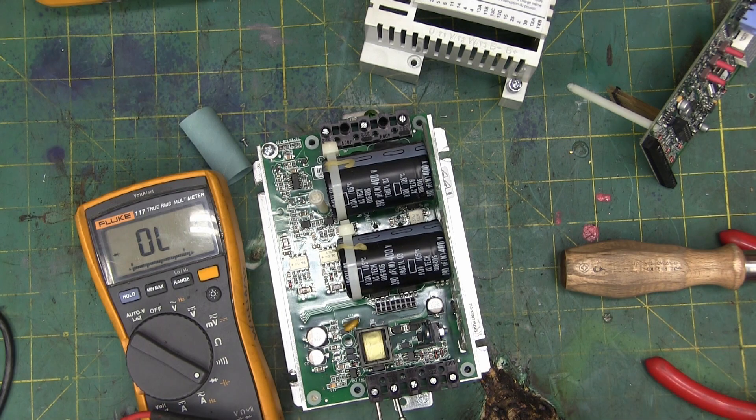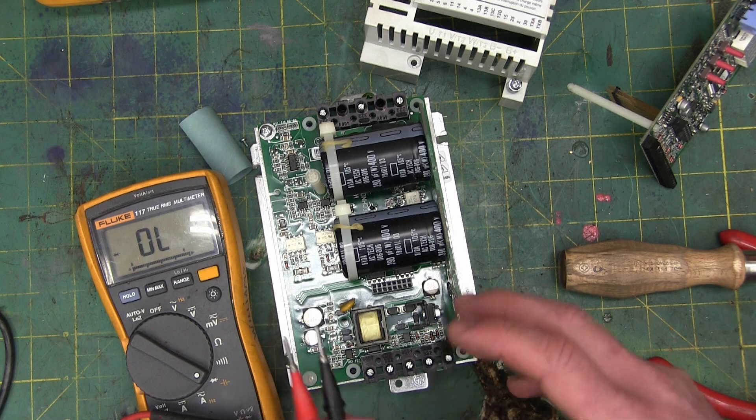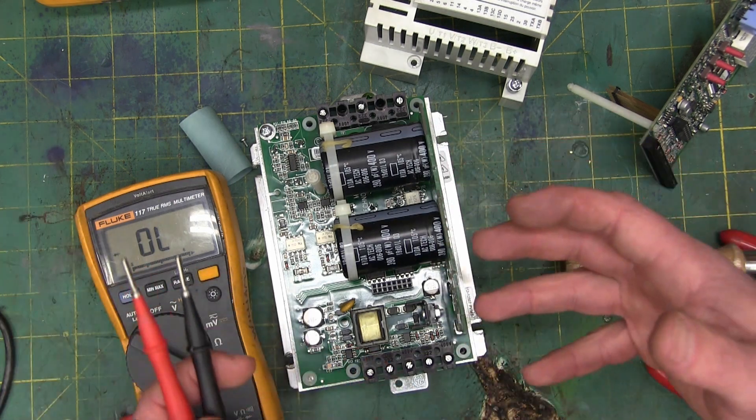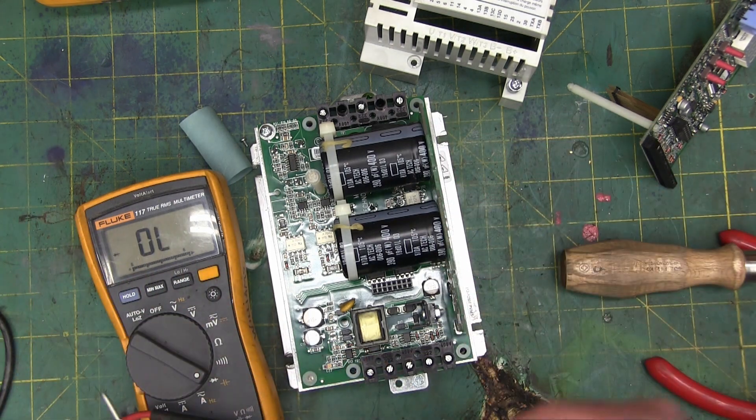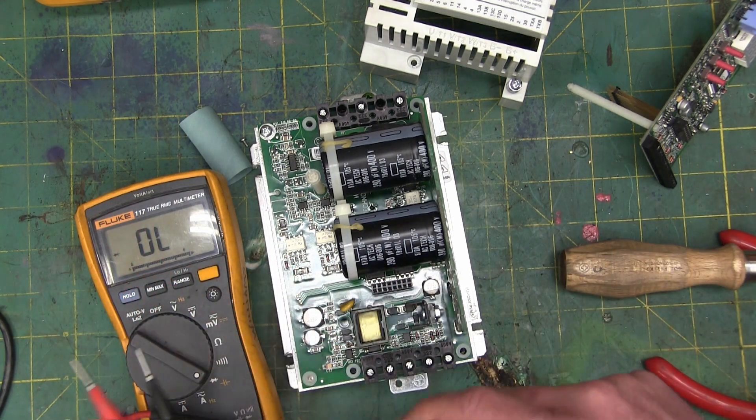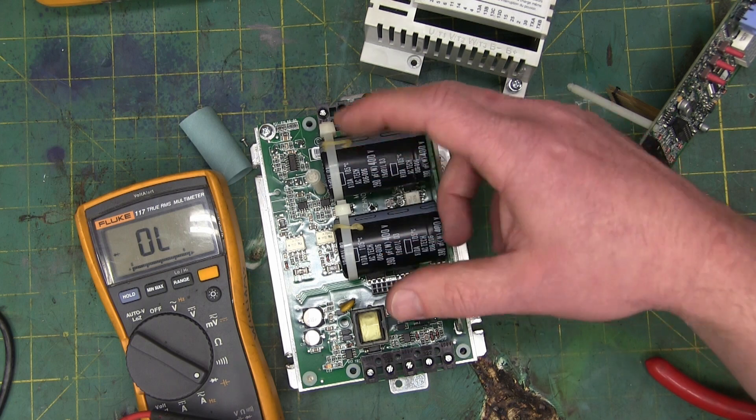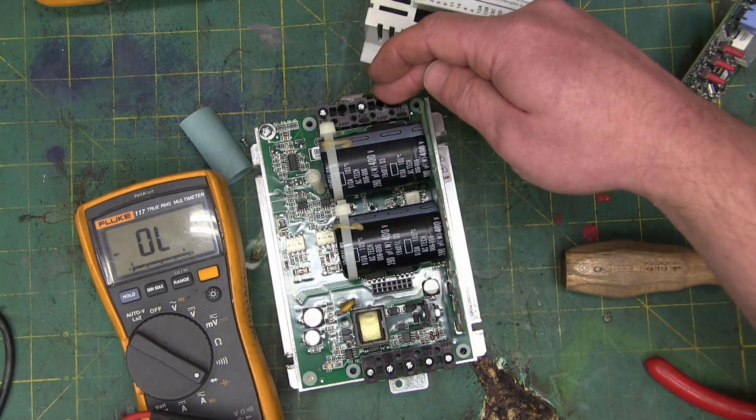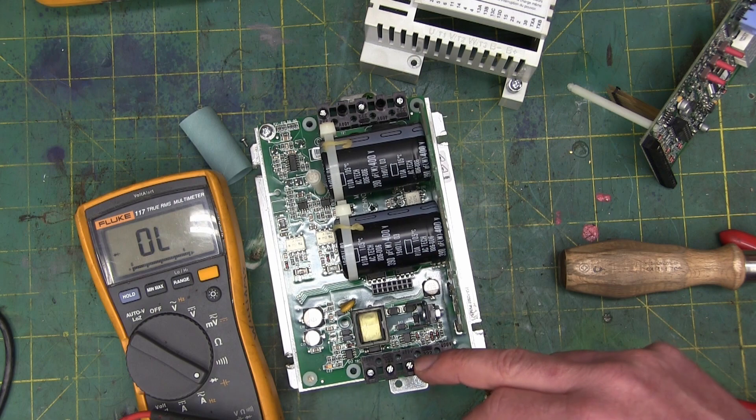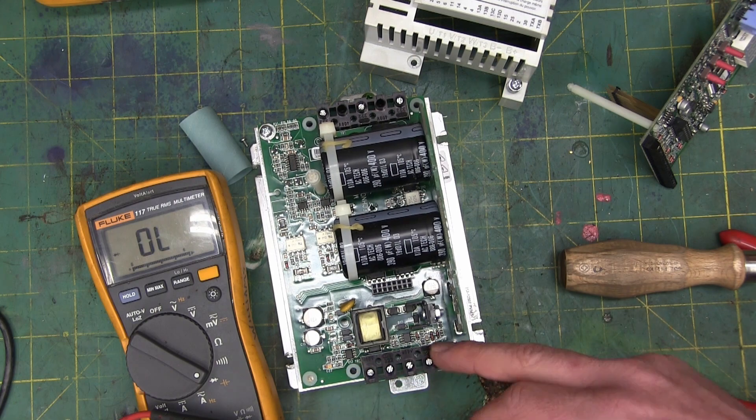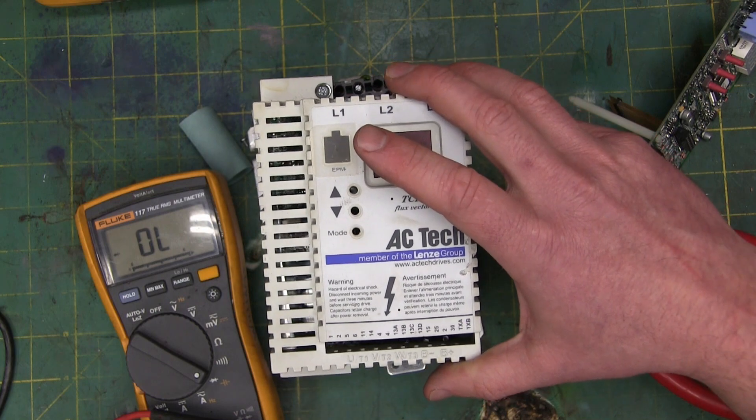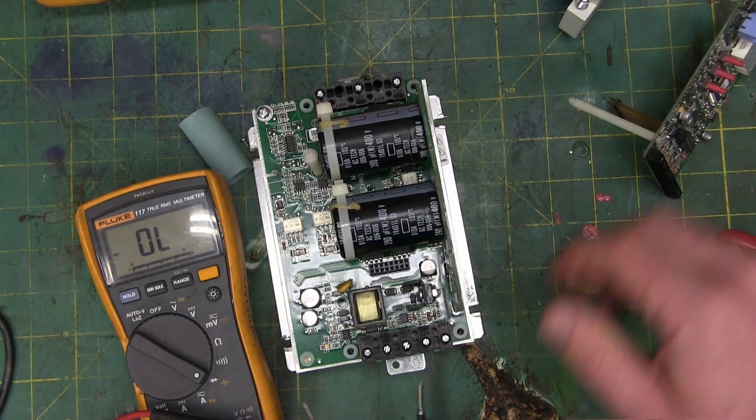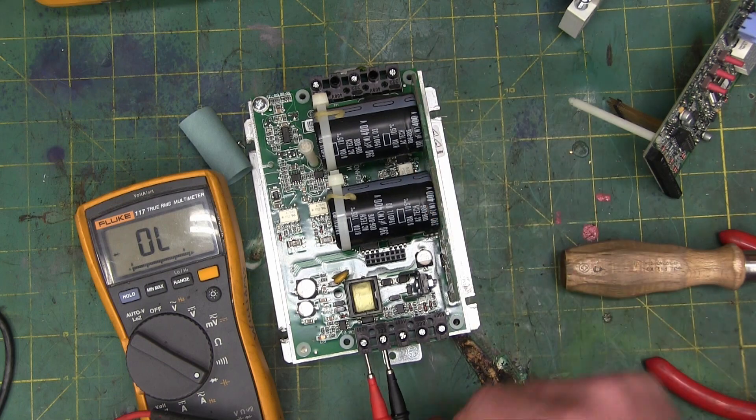In my haste, my teenage prom night ebullience, I jumped the gun, pun intended. What we can do here, the easiest thing first to troubleshoot, of course, you always want to do the easiest thing first. Just grab your meter and check the diode packs on the input, because there's a rectifying bridge on the input, of course, and check the diodes, the freewheel diodes, of the IGBT bridge. And we check the output phases, T1, T2, T3, or if you're German, U, V, and W. And we check the diode packs here.